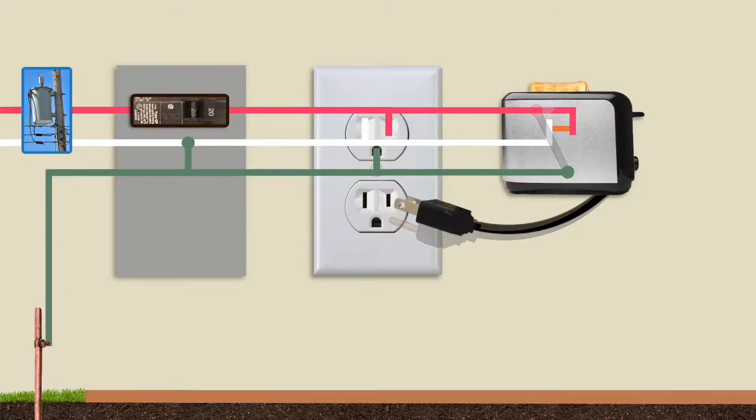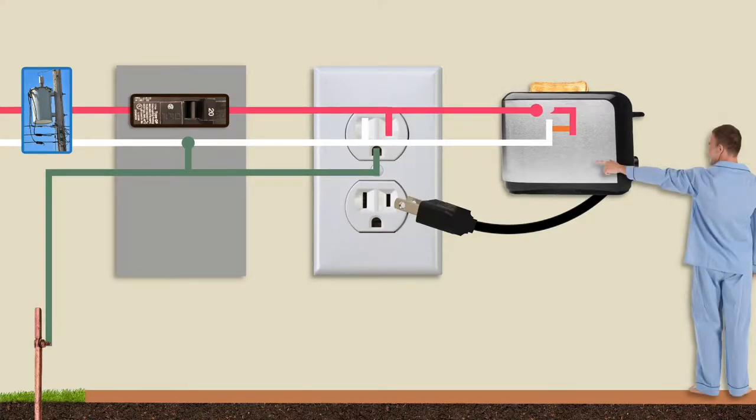With a two-prong plug, no ground connection exists between the metal case and the ground terminal, so if the hotline breaks and touches the case, and a person also touches the case, especially if they're in bare feet or somewhere damp, they'll receive a shock.